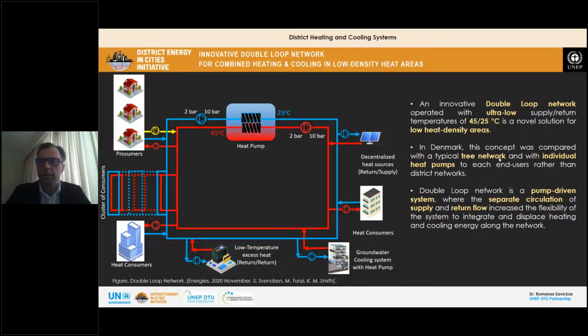model which operates with ultra low supply and return temperatures, about 45 supply and 25 return. It's mainly for low heat energy density areas. In Denmark, this solution was compared with a typical tree network and with individual heat pumps for each end user rather than district heating networks. The double loop network is a pump driven system where the separate circulation of supply and return flow increases the flexibility of the overall system.